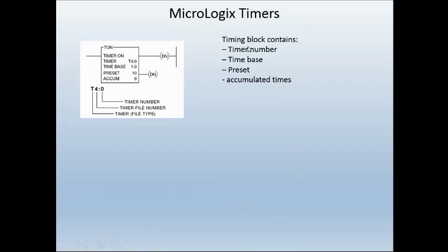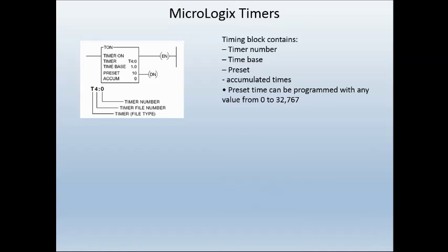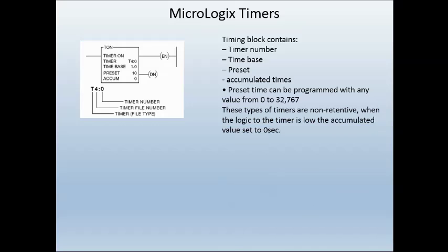Now let's look at our MicroLogix timers — this is true for a lot of the timers in RSLogix 500. This is the instruction here, it's a TON — a timer on. The timing block contains the timer's number, and each timer should have its own number. We have our time base; in this instance it's 1, so that tells me it's counting in seconds. You can change the time base to milliseconds or tenth of a second. We have our preset — that's the value you want your timer to time to — and your accumulated value, which is how much it actually has timed up until that point.